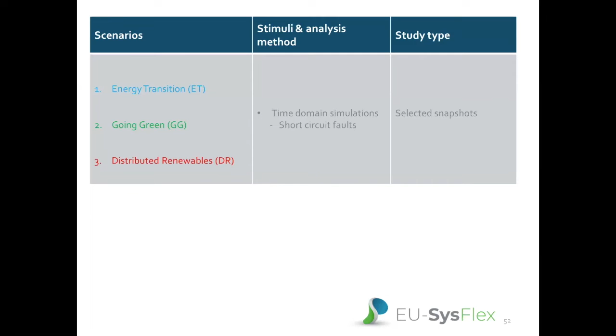We have applied sets of disturbances, assuming self-clearing closed three-phase short circuit events, both for analyzing synchronous generation modules and non-synchronous power park modules like wind farms, in order to assess how outages may influence the fault ride through capability of non-synchronous generation. We have also applied critical contingencies which have been identified in the voltage control analysis to the pre-fault power system operational state. As a result of the analysis, no voltage fault ride through requirement violations have been observed.